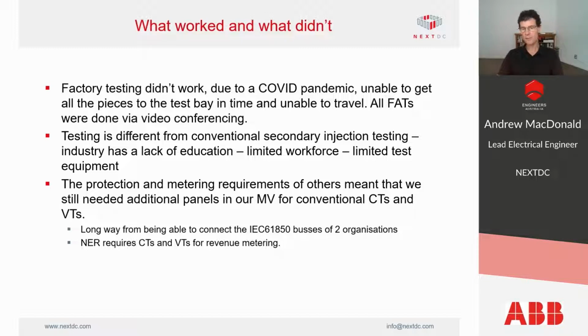The protection and metering requirements of other organisations meant that we still needed additional panels with space for conventional CTs and VTs in some of our medium voltage switchgear. We're a long way away from two organisations being able to link the 61850 buses and share protection information that way, and the national electricity rules require CT and VT for our revenue metering, which meant that we still had to use conventional CTs and VTs for that purpose.